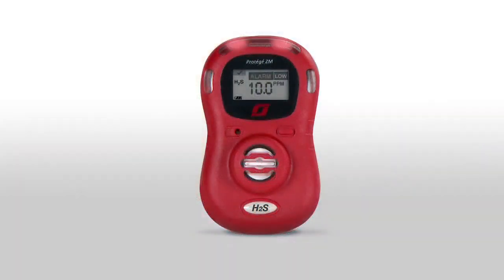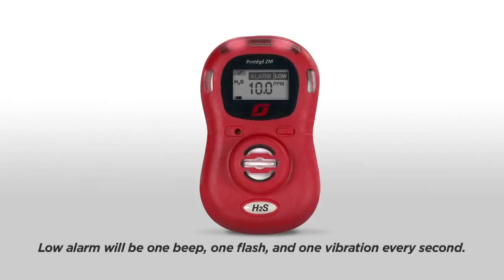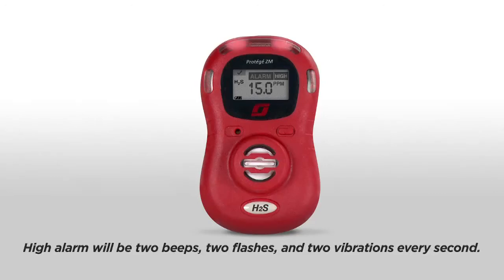If either of the alarm set points have been exceeded, the monitor will detect a hazardous environment and go into alarm. The unit will vibrate, emit an audible alarm, and the alarm LEDs will light up. The alarm message will be displayed on the LCD. If the low alarm has been triggered, the audible alert will be 1 beep, 1 flash, and 1 vibration every second. If the high alarm has been triggered, the alerts will be 2 beeps, 2 flashes, and 2 vibrations every second.